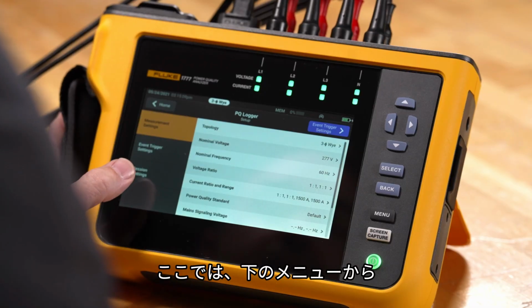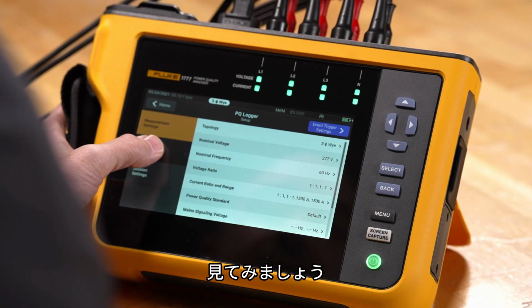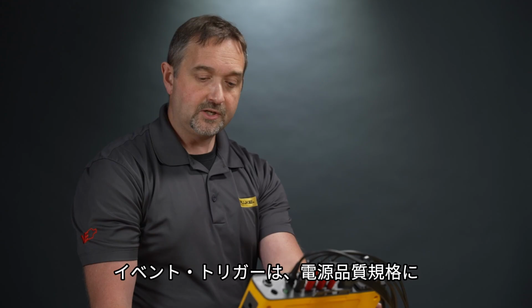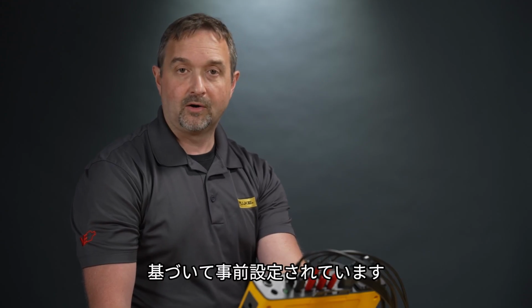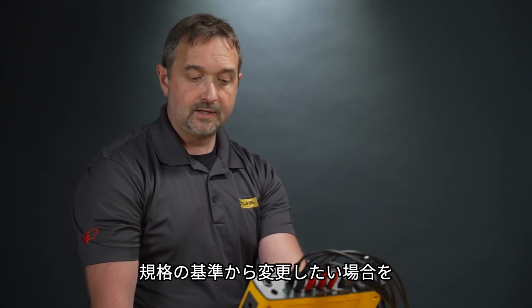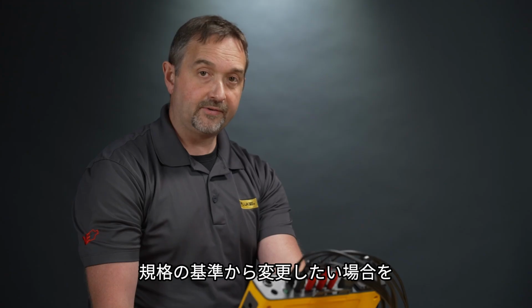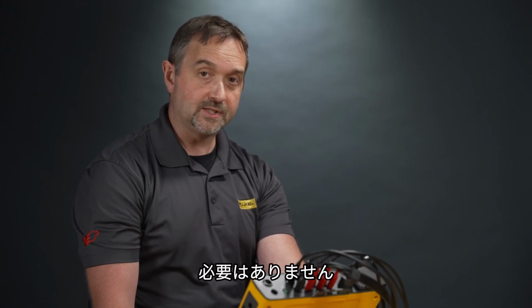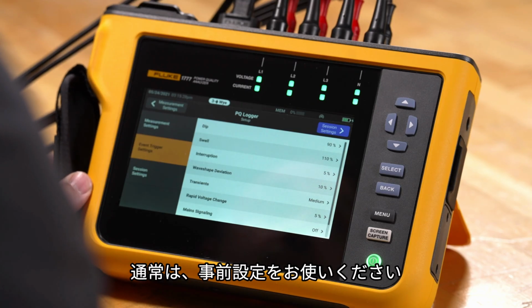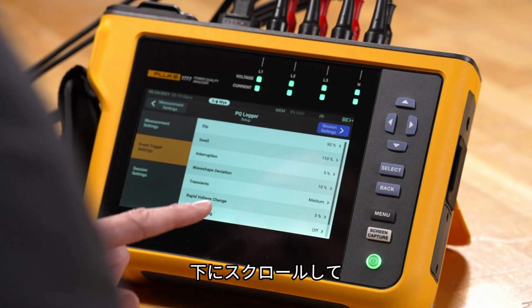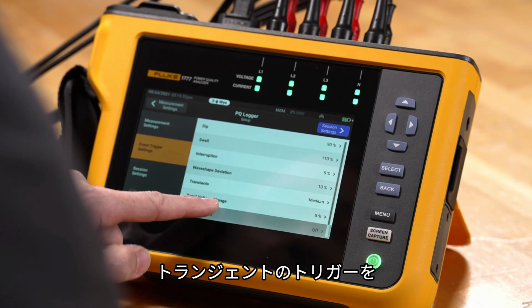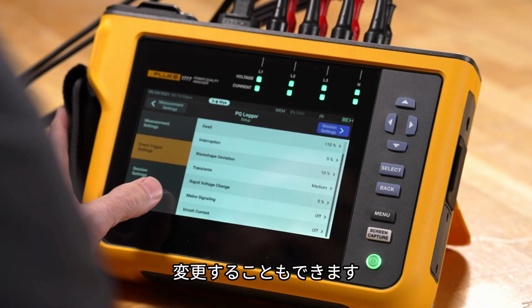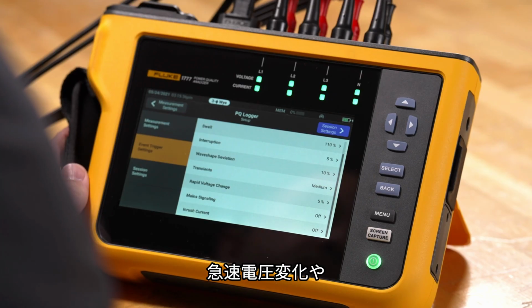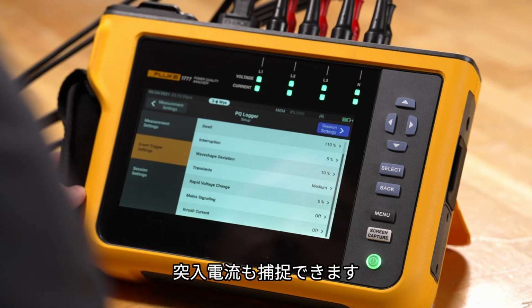But what we're going to do here is go down and take a look at our event triggers. Event triggers are already preset based on a power quality standard for you. So you don't actually need to modify these unless you want to make changes from a standard. We also have the ability to scroll down and make modifications to the transient triggering. We have rapid voltage changes as well as inrush capture.